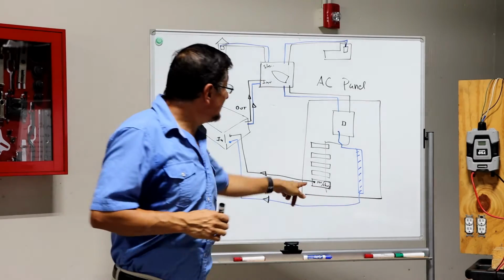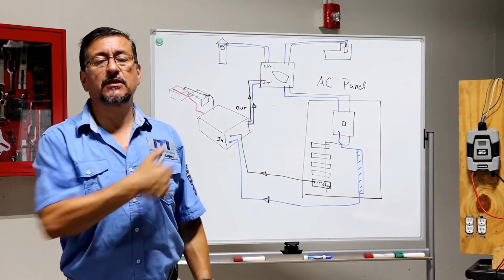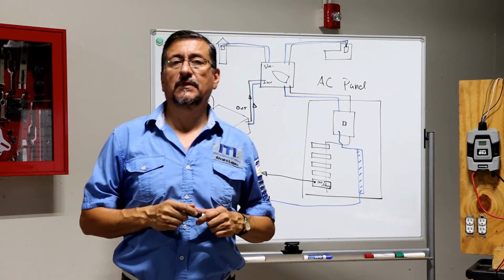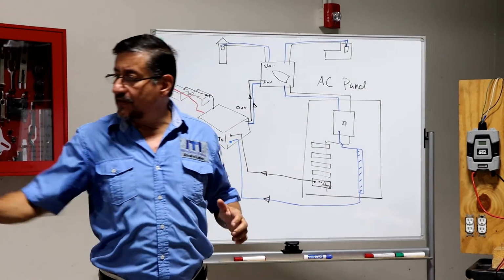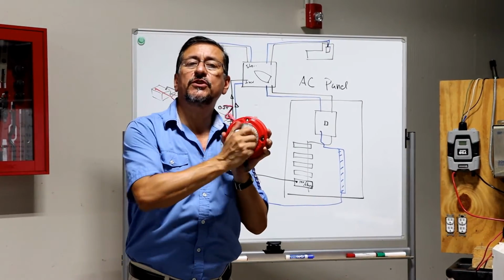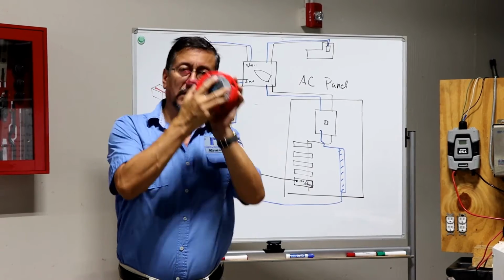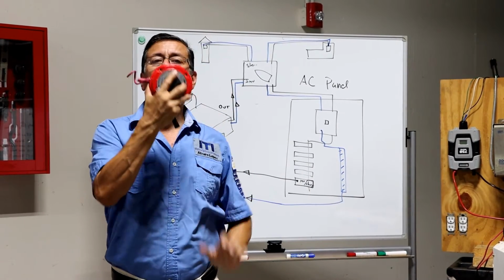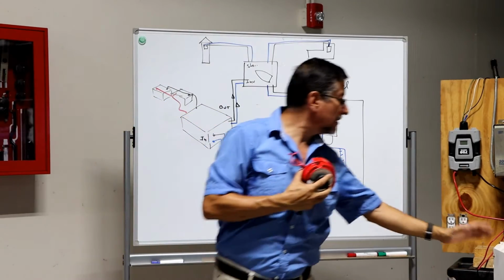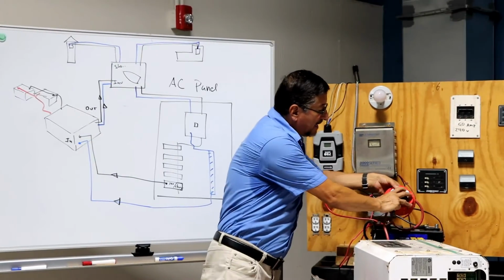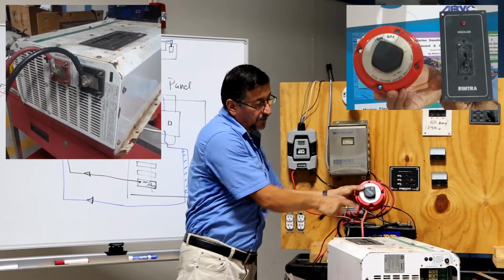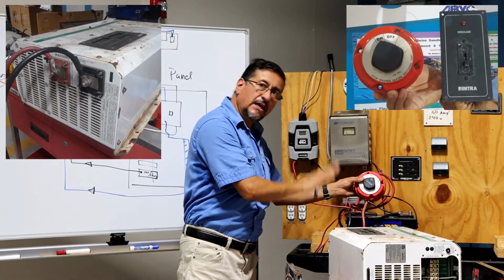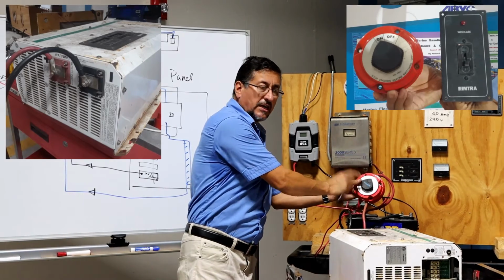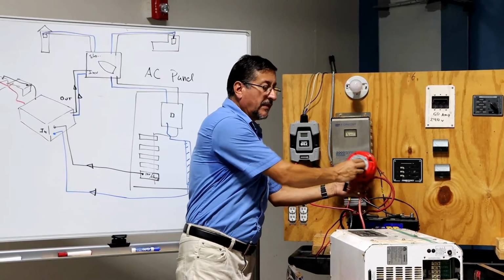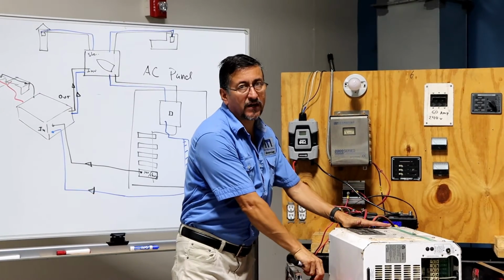Some people say this is the breaker in order to activate the inverter. No. The inverter is activated, remember, from the switch selector that supplies the DC power. This is the breaker or switch selector used to activate the inverter. The switch selector is located here in order to interrupt the positive at the input of the inverter. That's the input. In some cases you install one breaker instead of the switch selector. That's the breaker to activate the input of the inverter.